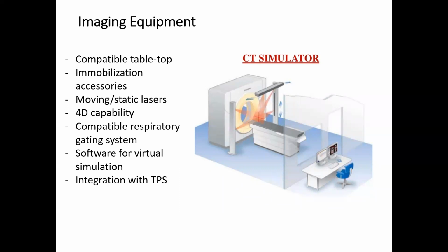So this is one point to consider, that the 4D capability of the CT simulator should be fully compatible with the treatment planning system. The same applies to the compatibility of the respiratory gating system. Certain CT scanners do have respiratory gating, but the time amplitude curve is not compatible with the curve of the machine. So the treatment planning system needs to generate a new curve for that, which is a big source of error.